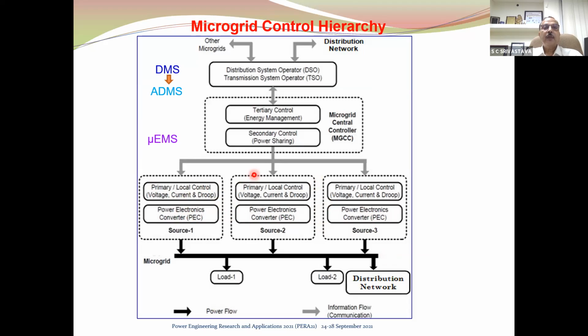Secondary control is basically the power sharing between different sources, and also the optimal management with respect to storage, looking at the load value. So there's some kind of communication or distributed control philosophy there. Then tertiary control—if you have several microgrids of this nature, their respective scheduling is required, coordination is required, volt-var control is required. That is normally done at the control center, where a distribution management system or advanced distribution management system is provided. So these are the three levels of control.